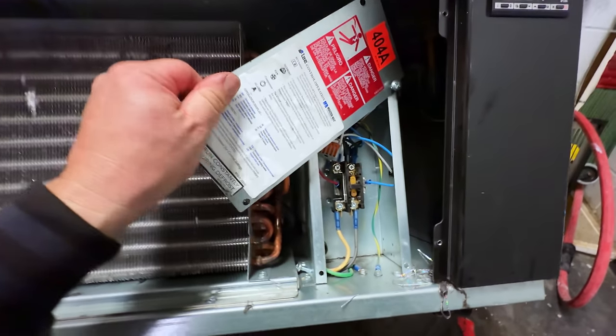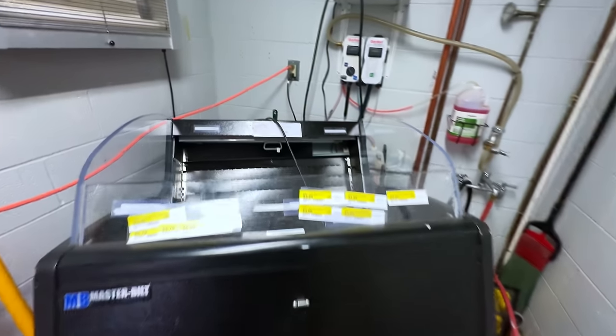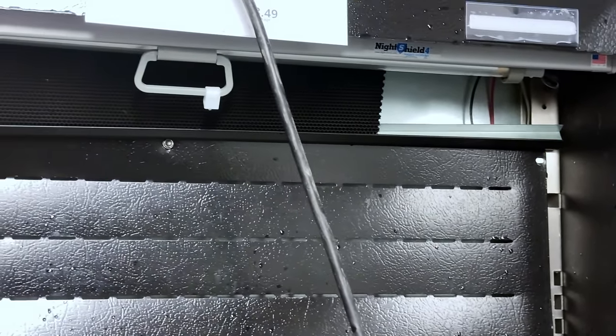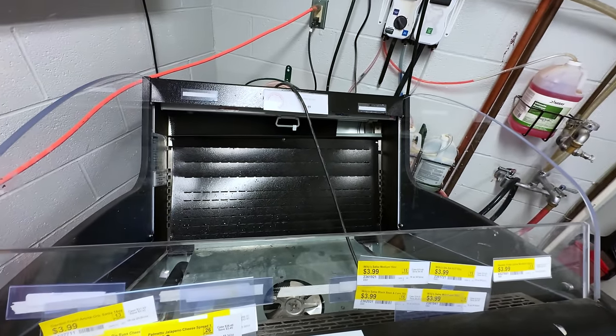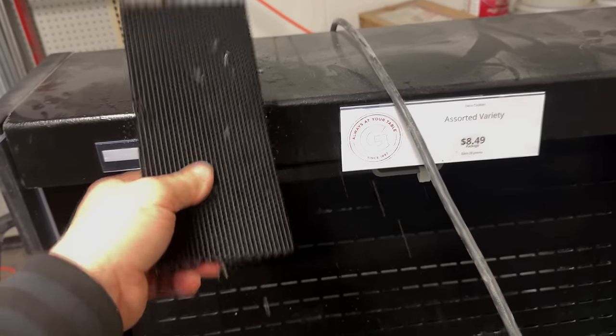Got a good look at it here. You can see that the contactor looks a little bit burnt. I'm not going to say that has anything to do with it. But the little honeycombs here — they were loose in there. We've got to finish doing some adjustments on those and get them back into place. When I first got here, you'd push them back and they'd just fall back; they don't have a track that they're actually in. The honeycomb was hardly even in place when I first got here.